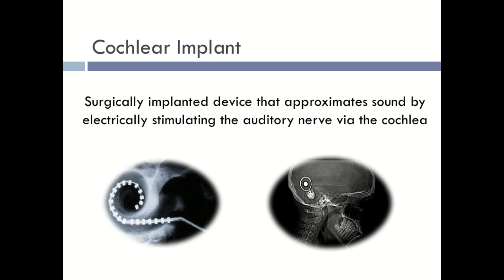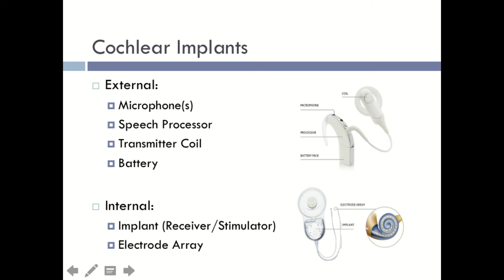Some details on the equipment. The external piece, so that would be the piece you see on your ear or worn over the ear, contains a microphone to pick up the external sound, a speech processor that's going to separate the signal from the noise, and a transmitter coil to transmit that signal over to the internal piece of the implant. The battery compartment is located at the bottom, and that's a rechargeable battery that's designed to last about 20 hours per day before recharging. On the internal side, we have a receiver stimulator. That is what transmits the sound down this electrode, eventually to the cochlea that's exciting the nerve.